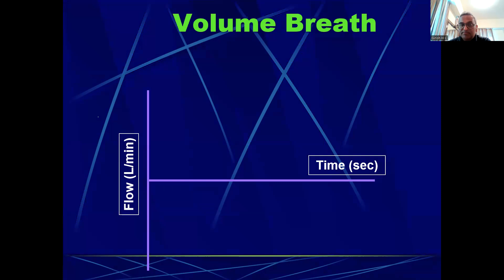Whereas on a machine, we breathe something like this. As I told you, the constant flow. And again, as you can see, exhalation is always passive, determined by the recoil of the lung and the chest. So it is only the inspiration which is supported by the ventilator. There is no ventilator made which actually helps in exhalation. Of course, to an extent, with the high frequency oscillator, because of the oscillations, you can say the exhalation is supported, but there is no ventilator made which can help in exhalation. All the ventilator does is help the inspiratory part.